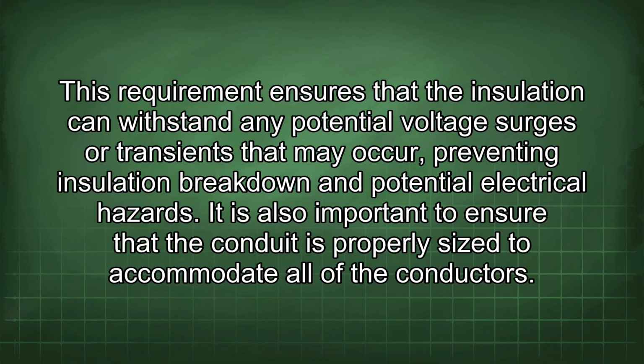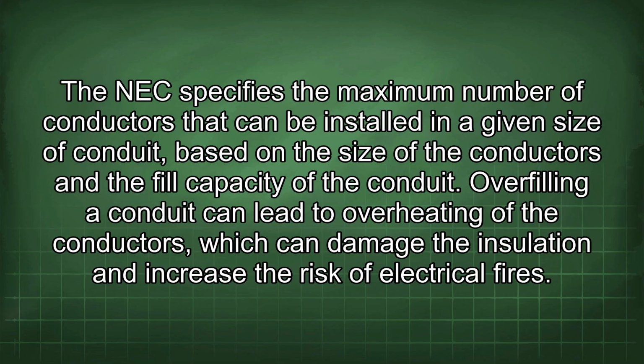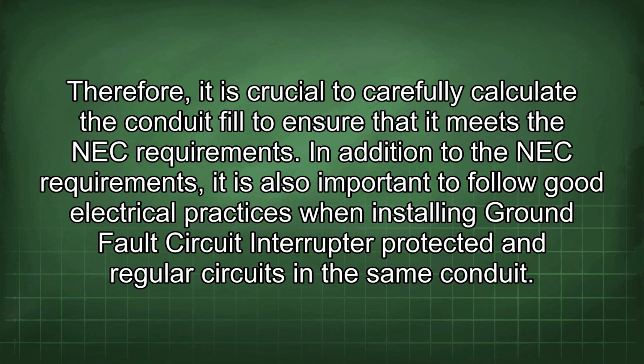It is also important to ensure that the conduit is properly sized to accommodate all of the conductors. The NEC specifies the maximum number of conductors that can be installed in a given size of conduit based on the size of the conductors and the fill capacity of the conduit. Overfilling a conduit can lead to overheating of the conductors, which can damage the insulation and increase the risk of electrical fires. Therefore, it is crucial to carefully calculate the conduit fill to ensure that it meets the NEC requirements.